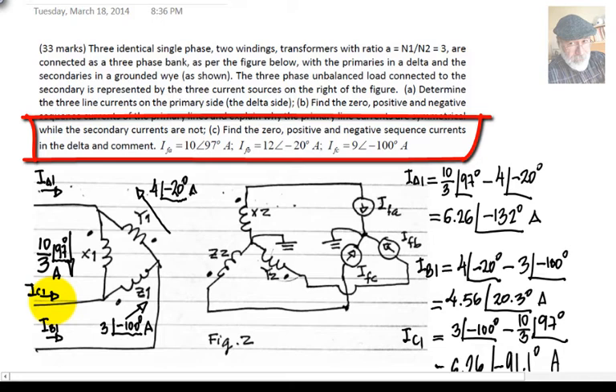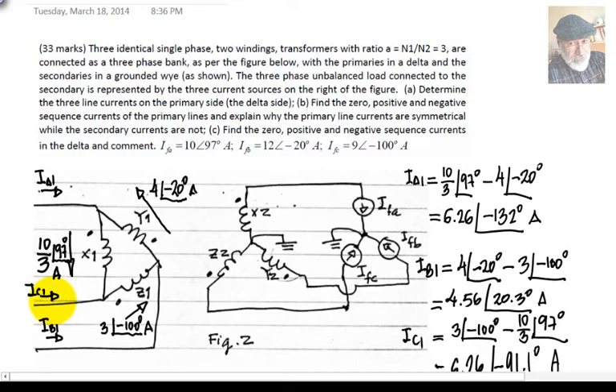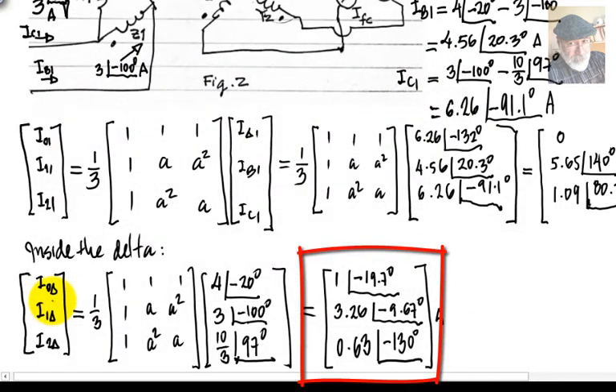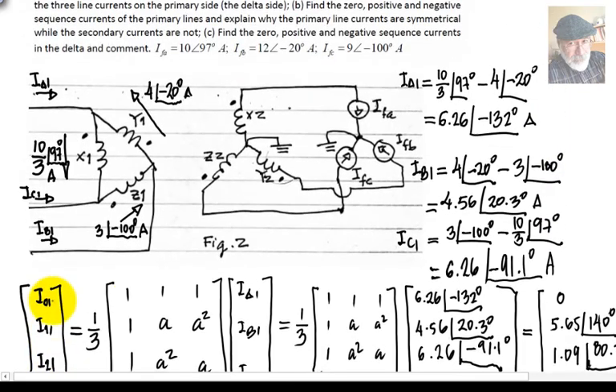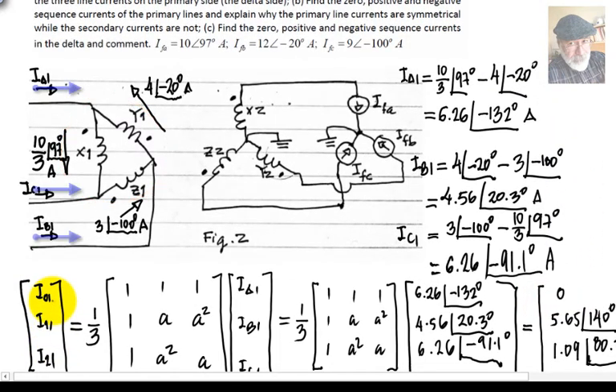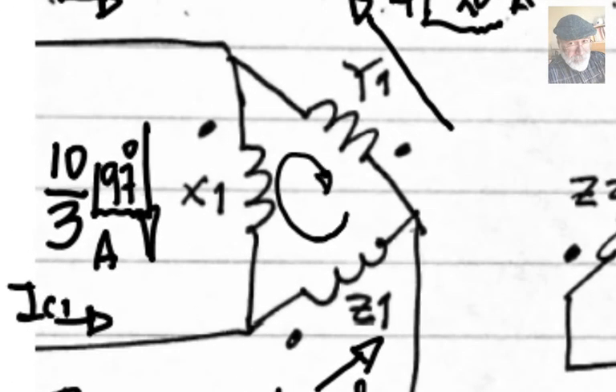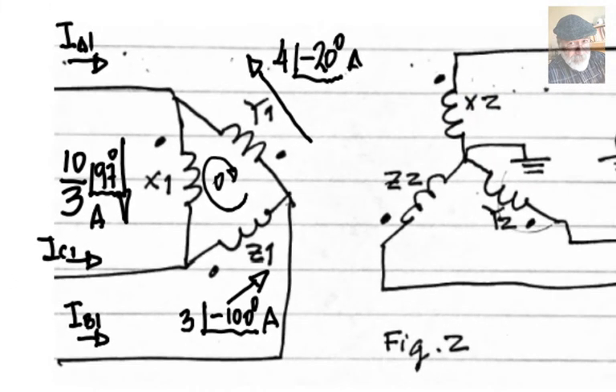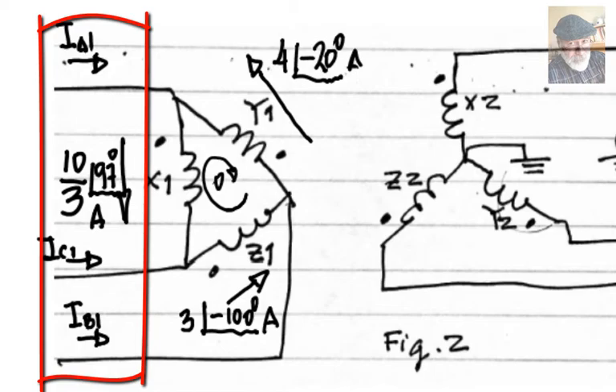In Part C, find the zero, positive, and negative sequence currents inside the delta. You can see those three currents in the delta. Apply the phase-to-sequence conversion to those to obtain the zero sequence, positive sequence, and negative sequence inside the delta. What happens is that there are zero-sequence currents — one amp — inside the delta, but no zero-sequence current in the line. The reason is that the zero-sequence current circulates inside the delta but never leaves it. So there are no zero-sequence currents in the lines connected to a delta winding of a transformer.